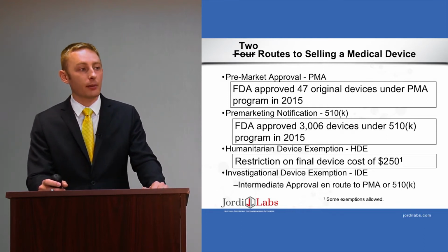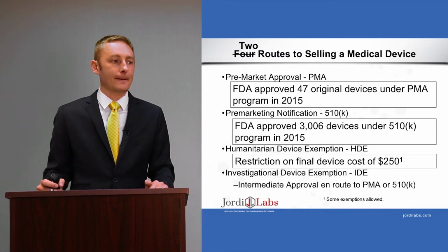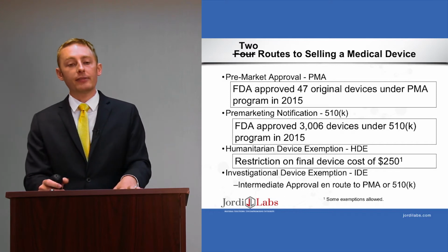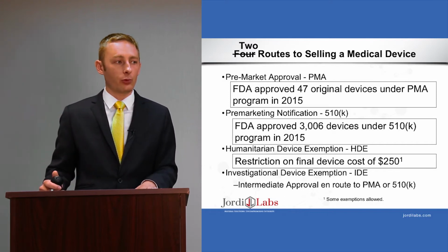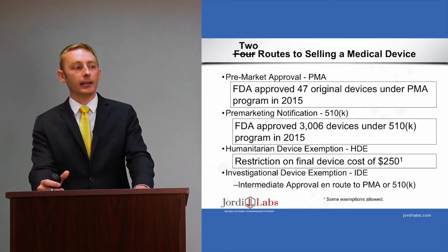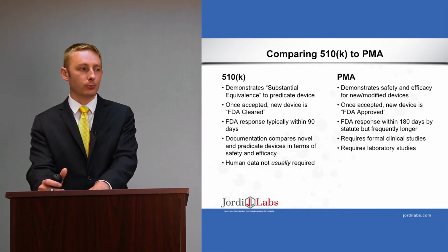In contrast, they approved over 3,000 devices through the 510K process. And so what I'm trying to get at here is a 510K is pretty much the route to go for your medical device. And to illustrate that, here are the differences between the 510K and the PMA programs.